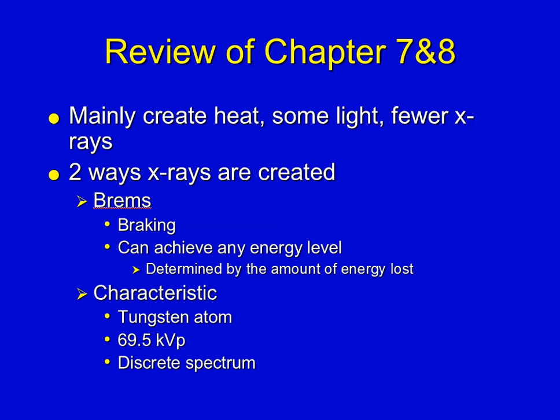Bremsstrahlung X-ray creation can occur at any energy level — it's determined by the amount of energy lost. If you set 100 kVP and the electron loses all of its energy, the X-ray photon created is 100 kVP. Most electrons won't lose all their energy, which is why on the Brem spectrum there are very few high-energy X-ray photons.